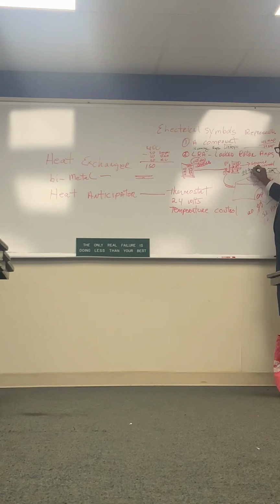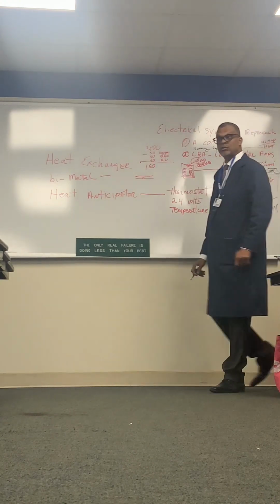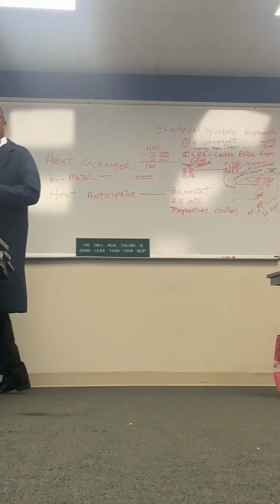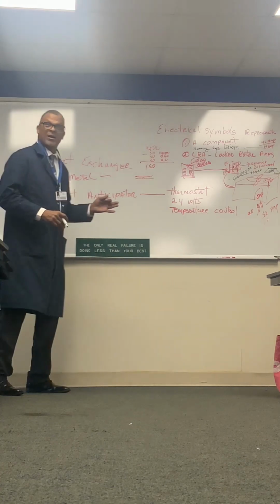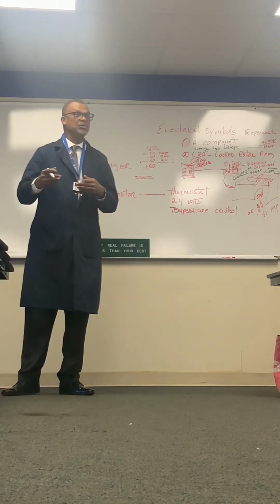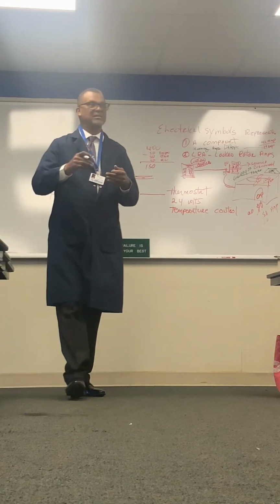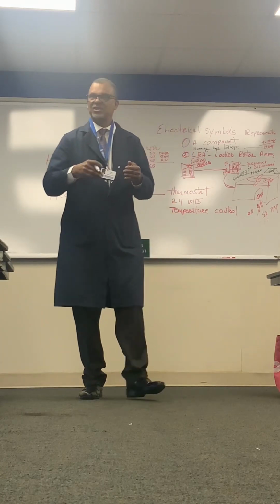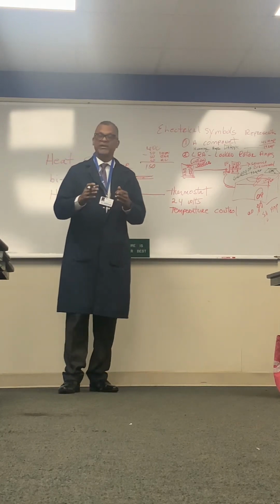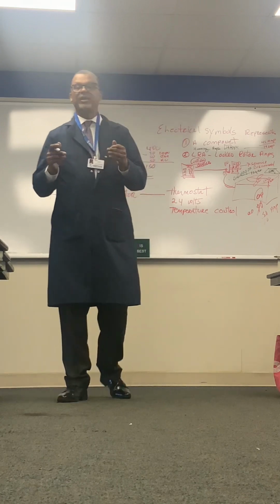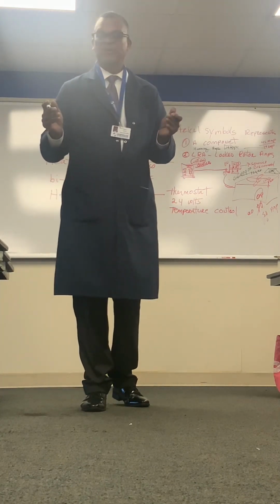Okay, so if it's 99 degrees Fahrenheit ambient, is 99 degrees cooler than 124 degrees? Yes. So you need to know that, because you could say, well, how could it remove heat? It's almost 100 degrees out here. Well, we're bringing to it in this coil 124. So it still goes from a warmer to a cooler. That's why I don't like to say hotter to a colder. It's just a difference of temperature, and the greater the temperature difference, the cooler it becomes.